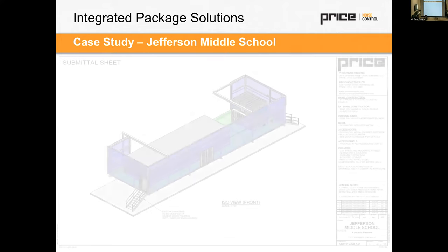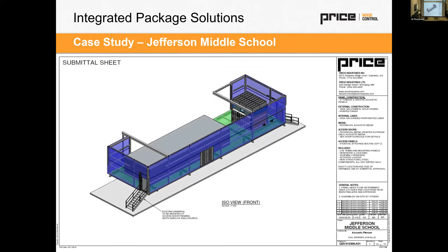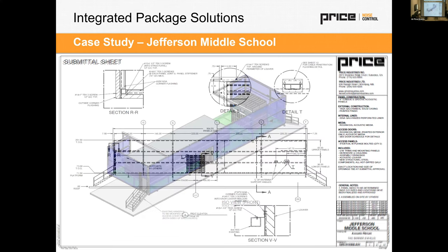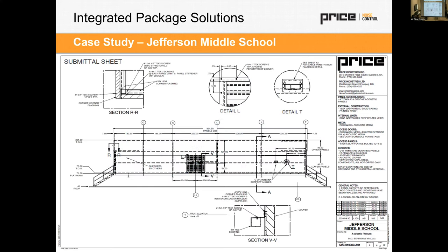You added all that steel? So that was pre-construction. This was our design that we came up with, which was basically a fully enclosed barrier wall with new steel being added to brace and hold everything up, and then a silencer package on the chiller, like we often do for controlling the compressor and the condensing fan noise. How much did that cost? Good question. I'll get to that.